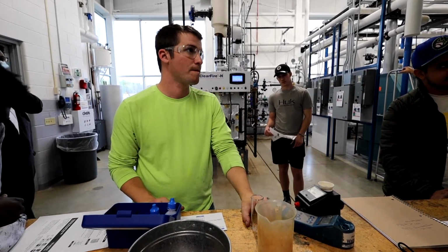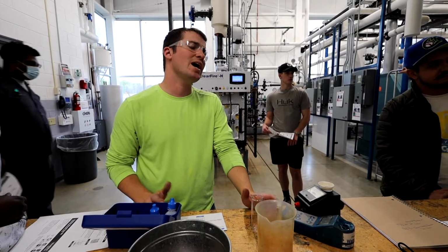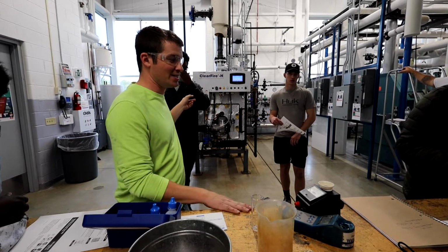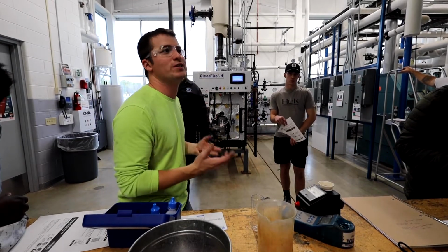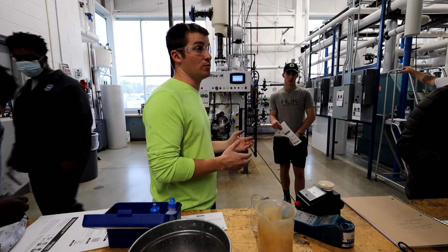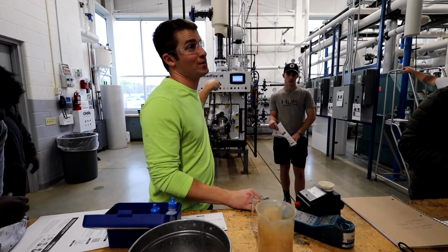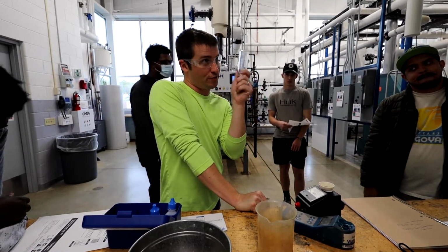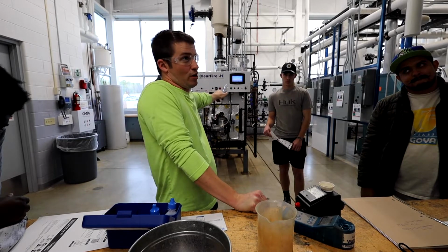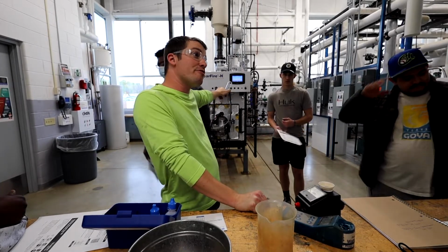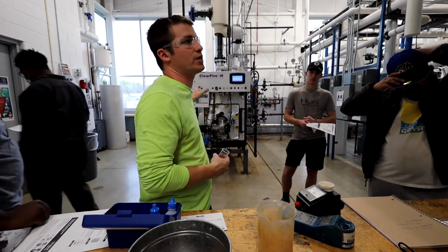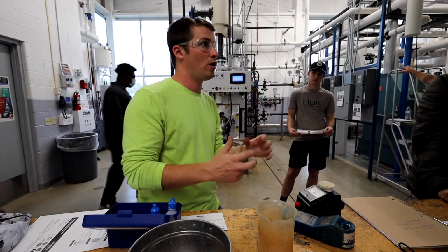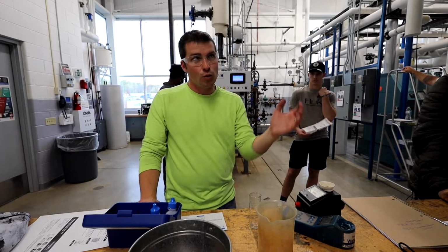So even if you just put 2 drops in, you clear that? Yeah. The anti-scalant in there is designed to handle some hardness. It's just we can't put 100 parts per million of hardness in the boiler because whatever I put into it, I'm concentrating. So if I'm running 10 cycles of concentration, and we have 4.5 parts per million of hardness in our feed water, that means we have 45 in our boiler. So if we're putting 100 in, we have 1,000, right? And then at that point, chemistry cannot handle it. It can't overcome that much stuff in the water, right? So that's why we're okay with some.